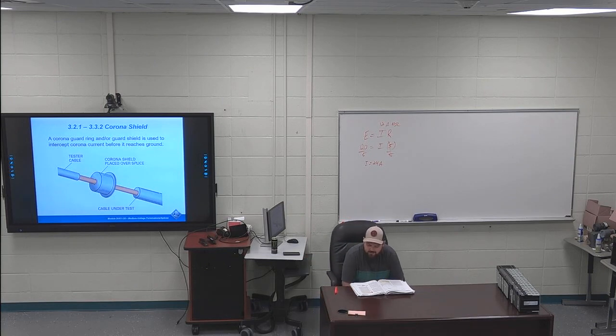And determine the maximum test voltage to use. And then going along with that, skip the next sentence, and I got 2 more highlights in this step 3. As a rough rule of thumb, proof testing is usually conducted at 60% of the factory test voltage. The next sentence is a separate highlight. Acceptance testing would call for a maximum value of about 80% of the factory test voltage. So that's for acceptance testing. Proofing is 60%, acceptance testing is 80%.